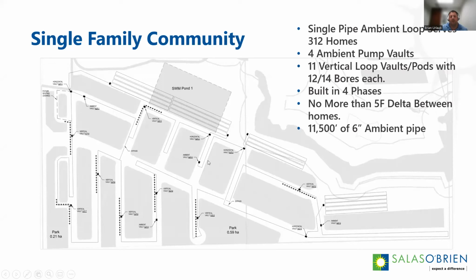As each house uses energy in heating mode, we're pulling heat off that single pipe. From one location to the next, we're trying to maintain a 5-degree or less delta T, meaning the homeowner closest to the first takeoff and the homeowner near the last takeoff before the next injection point will only see a 5-degree differential—negligible given the efficiency profile of a heat pump. They would never notice the difference from one utility bill to the next.